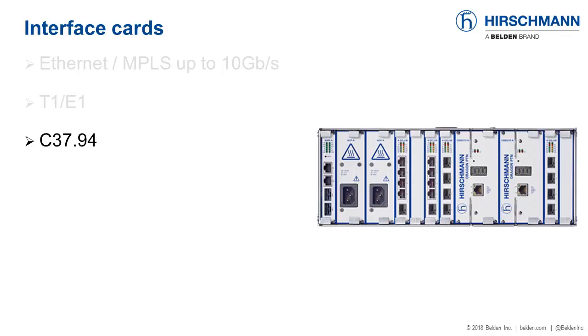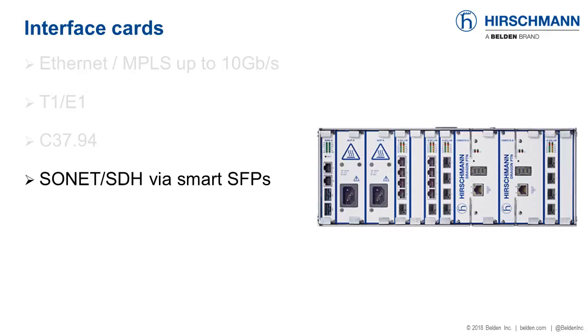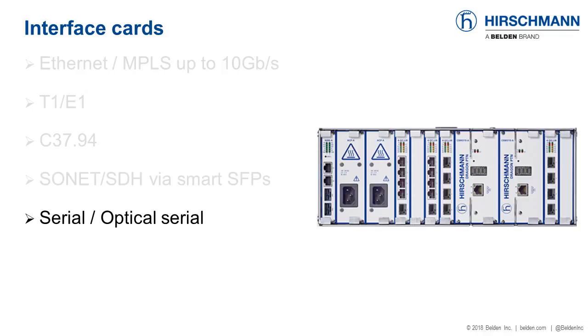C37.94 is a standard for transmitting multiple 64 kilobits per second channels on an optical fiber — a protocol used in the power industry between teleprotection equipment and multiplexer equipment. Smart SFPs enable transparent transportation of synchronous digital bitstreams from a SONET or SDH network. If you are planning to migrate your existing SONET or SDH network to a new MPLS-TP network, these SFPs provide a seamless transition method. Interface cards are also available to bridge serial links across the MPLS-TP backbone, supporting protocols including RS-232, RS-422, RS-485, X.21, and V.35 as well as optical low-speed serial.